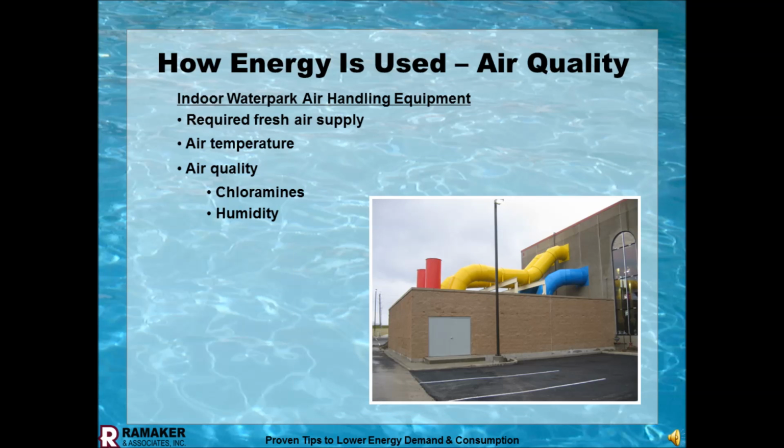Indoor water parks, the air handling units are huge. In this particular photo, behind the block wall, there are 2 air handling units. Both of them are the size of a good-sized Winnebago. I mean, you're talking semi-truck trailers. That size, they're big. And this particular water park was less than 30, it was 26,000 square feet. And the ductwork on it, 42-inch diameter, 48-inch, is just moving a boatload of air.